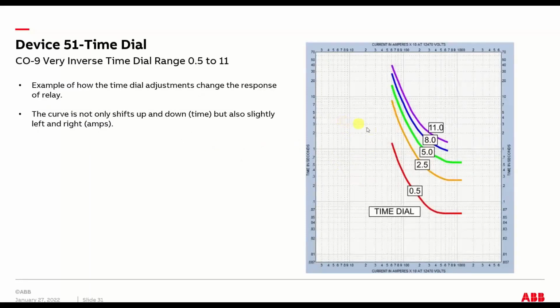Here's an example of the time dial adjustment. This is a CO9, which is a very inverse curve, and here are the different time dial settings. It's really meant to illustrate that in relays it's not a true up and down change in time. It's more of a slope to the left and right. So as you increase the time dial, the slope is actually moving up, but it's also moving a little bit to the right in terms of amps. So the way the curve looks kind of changes.